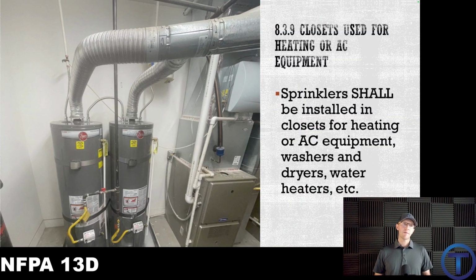8.3.9 specifies that closets used for heating or AC equipment do need sprinklers. It says sprinklers shall be installed in closets for heating or AC equipment, washers and dryers, and water heaters, etc. Obviously, we have these appliances that are using fire, that are using electricity. This is a high potential place for a problem, right? And because of that, even though I might not spend a lot of my time in that mechanical closet, I should have some sort of fire sprinkler to put out a fire there to protect myself in the building.